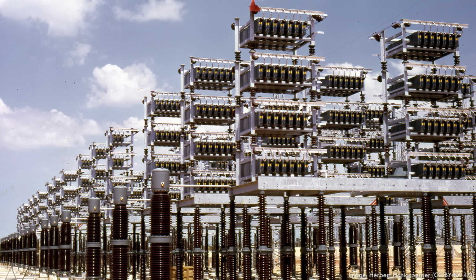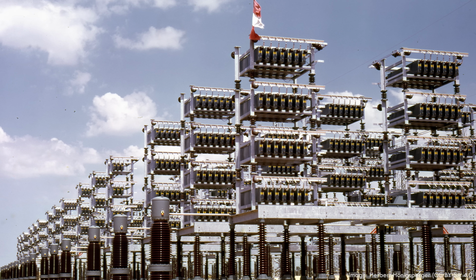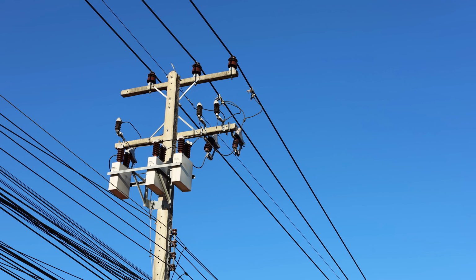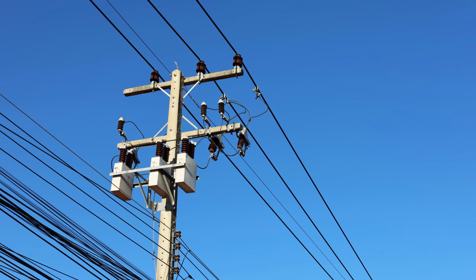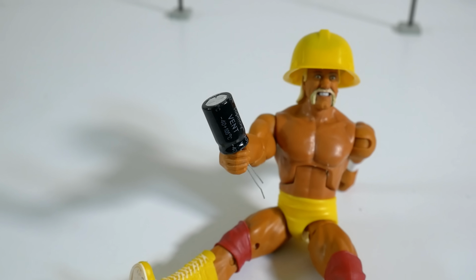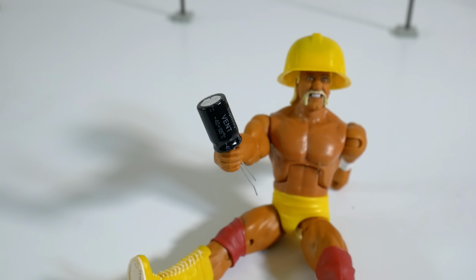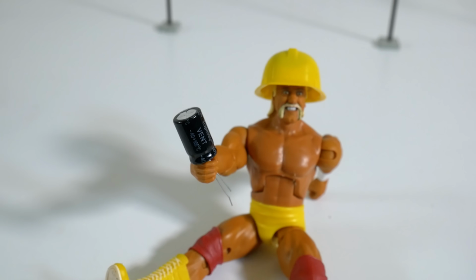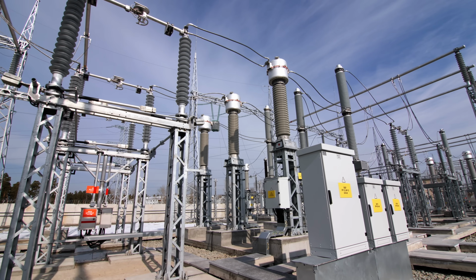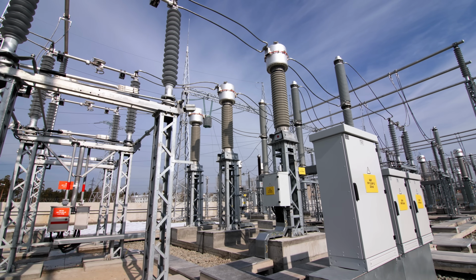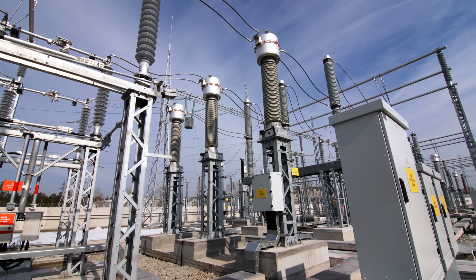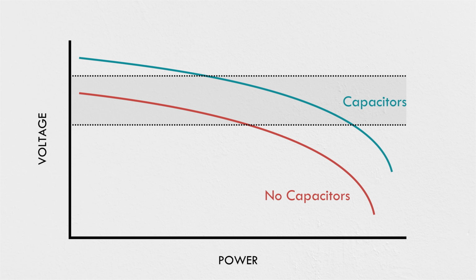Another option, and one you're more likely to spot, are shunt capacitor banks connected across the lines. Sometimes you can see them in substations, but many capacitor banks are installed on poles, out in the open for anyone to have a look. Like the capacitor in my demo, they increase the power factor and boost the PV curve up. That can actually become a problem during off-peak hours by boosting the voltage above where it should be. So many capacitor banks are switched on or off depending on system conditions. Looking back at the PV curve, you can see how leaving the capacitors off during periods of low demand keeps voltage within limits, and having them on when demand is high provides more margin and more voltage.